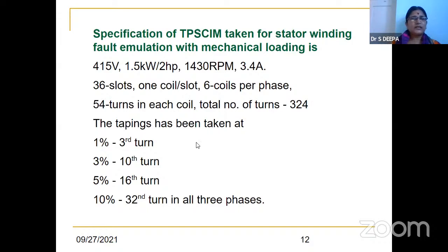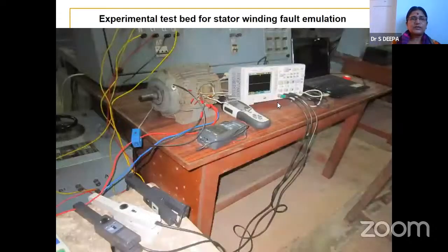The tappings have been taken at different percentages, because short circuit testing should be done at no load condition only. If we load it and do the experiment, it will burn off. So 1% means the third turn, 3% means the 10th turn, 5% the 16th turn, 10% the 32nd turn, in all three phases. So this is the specification.